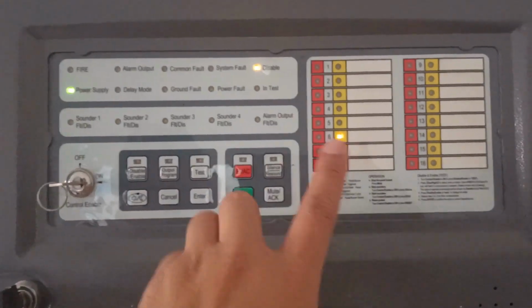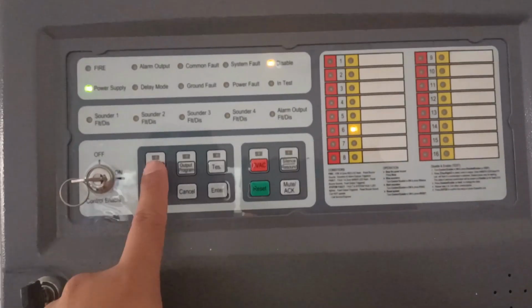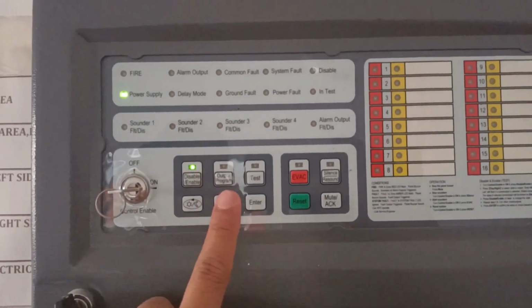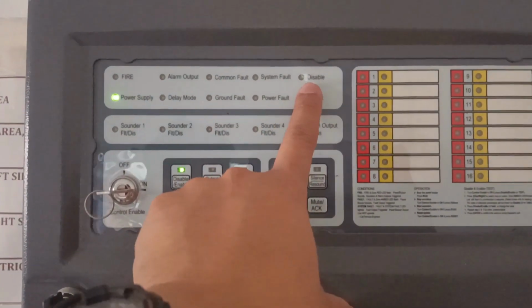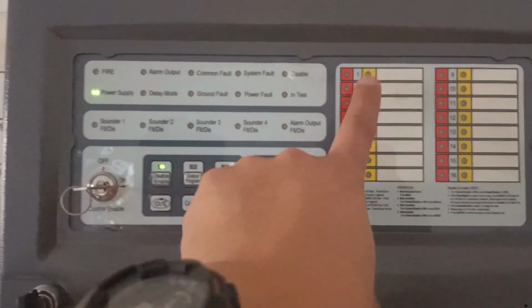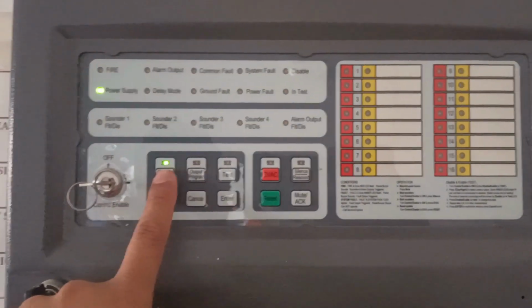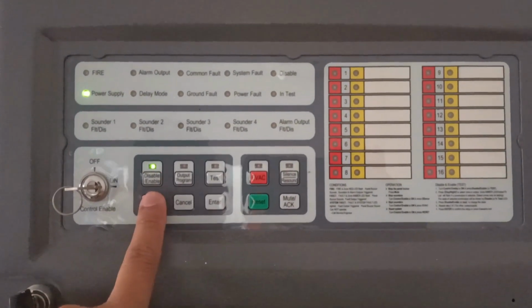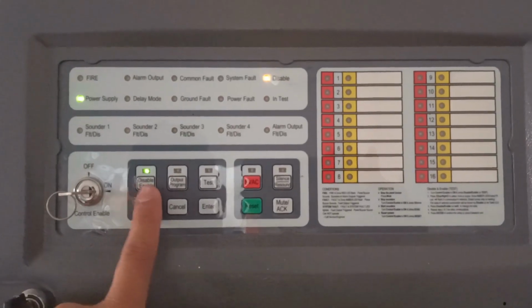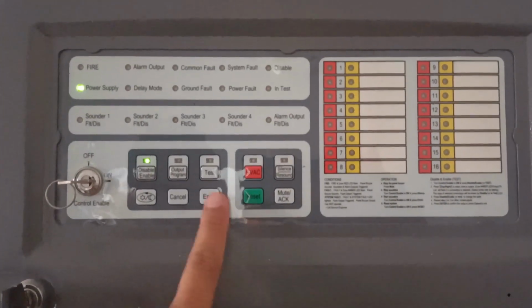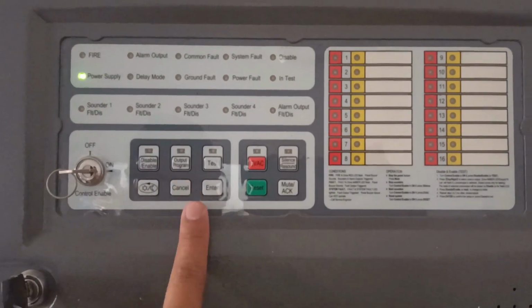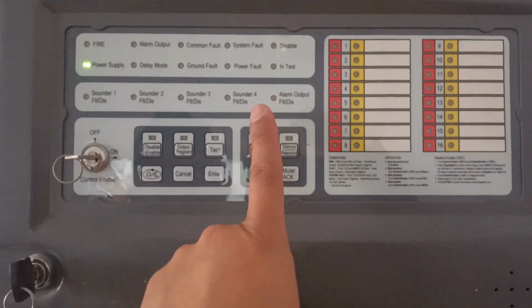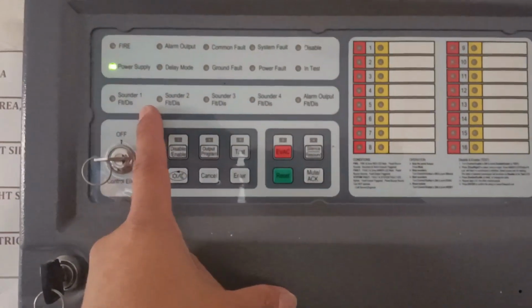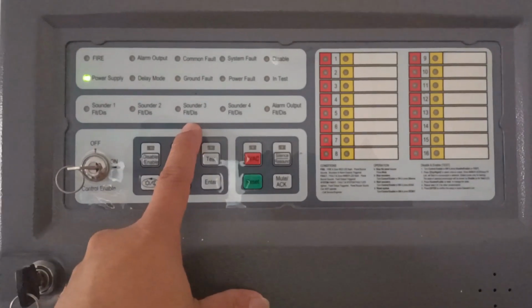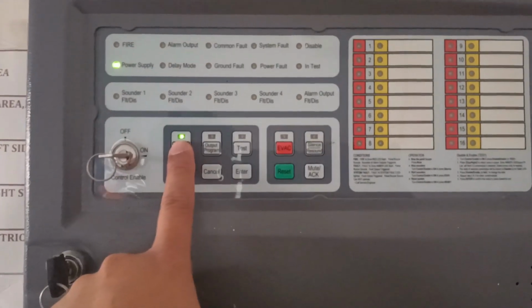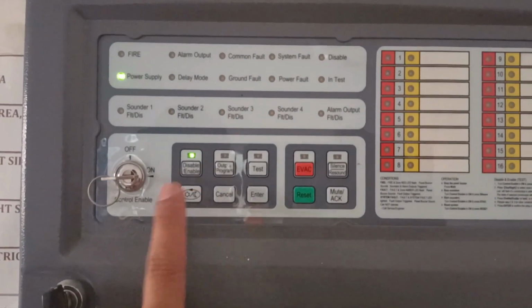So zone 6 is disabled. Then I will normalize the zone. I press disable again, one time. Then the disable light is gone. Then you press going down to zone 6, enter, enter, then cancel. So now it is normal.